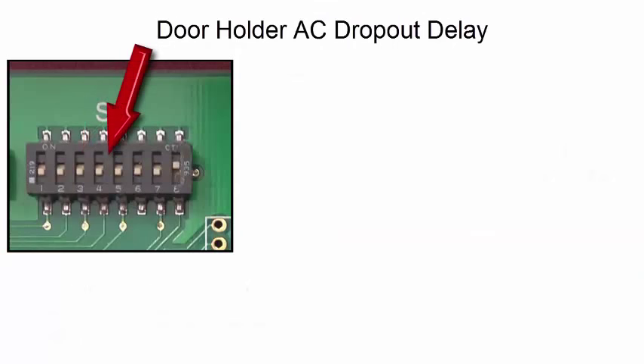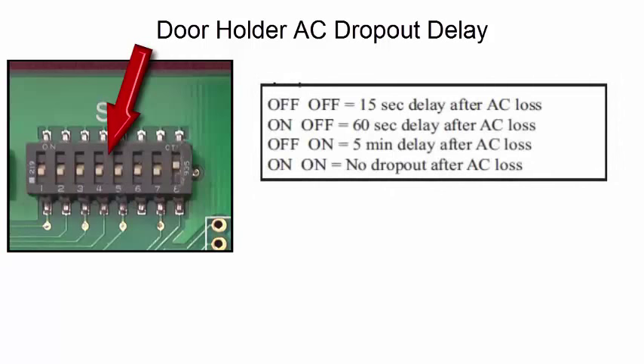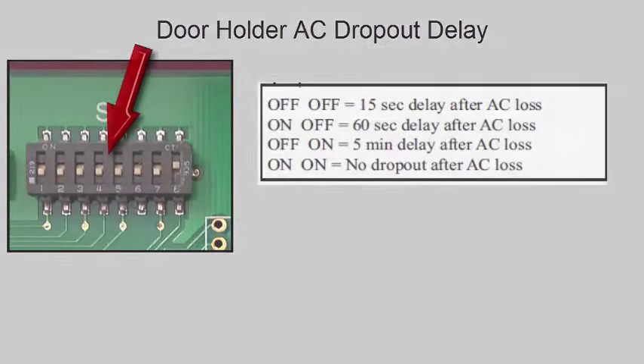DIP switch 4 and 5 are used to set the door holder AC dropout delay. When DIP switch 4 and 5 are both in the off position, there is a 15 second delay before the panel drops power to the door holder circuit. You can select the delay to be 15 seconds, 60 seconds, 5 minutes, or keep the door holder circuit energized on a loss of AC.